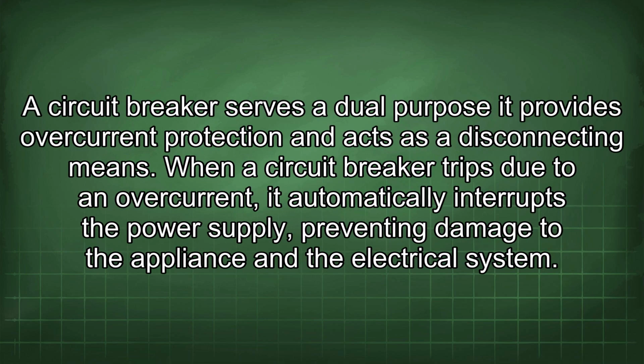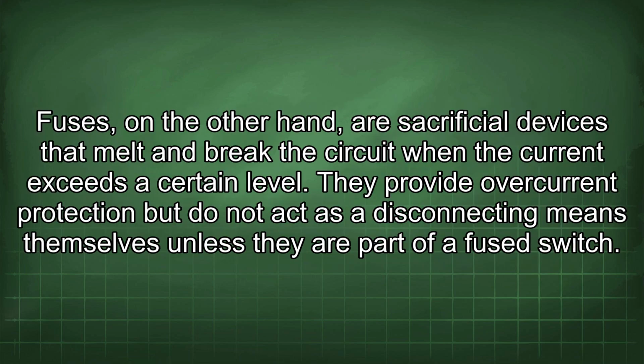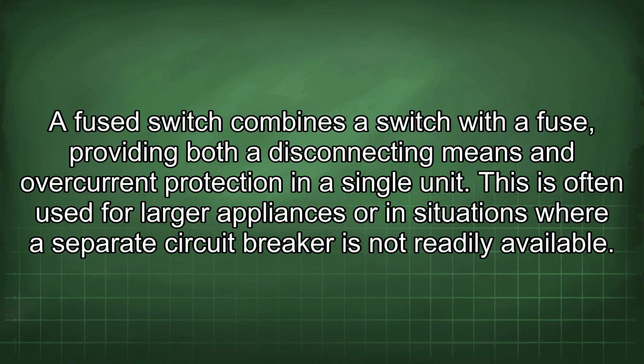A circuit breaker serves a dual purpose. It provides overcurrent protection and acts as a disconnecting means. When a circuit breaker trips due to an overcurrent, it automatically interrupts the power supply, preventing damage to the appliance and the electrical system. Fuses, on the other hand, are sacrificial devices that melt and break the circuit when the current exceeds a certain level. They provide overcurrent protection but do not act as a disconnecting means themselves unless they are part of a fused switch. A fused switch combines a switch with the fuse, providing both the disconnecting means and overcurrent protection in a single unit.